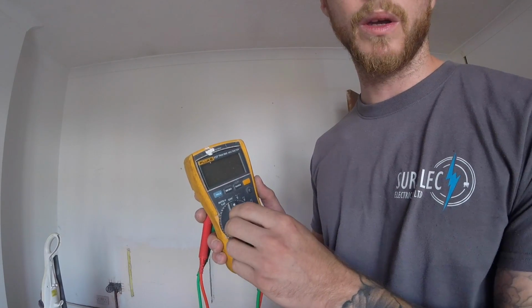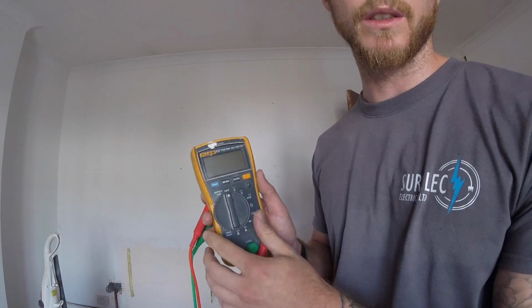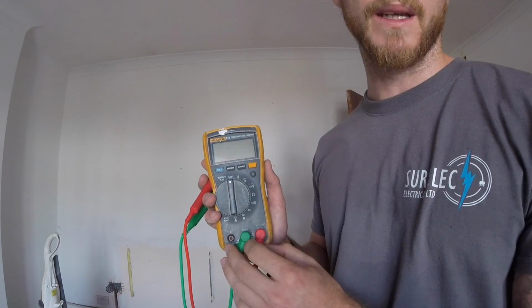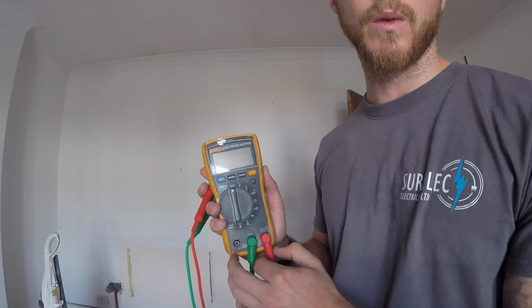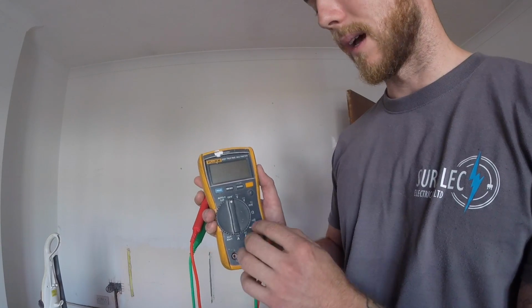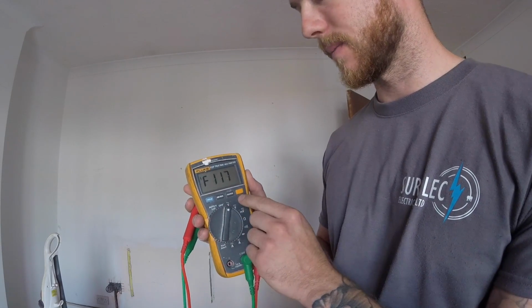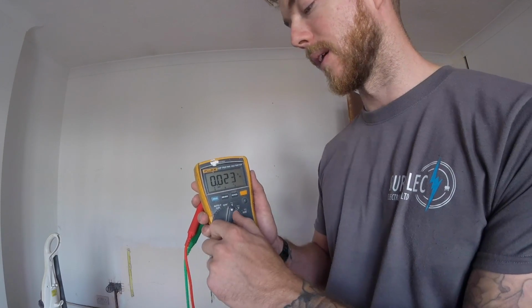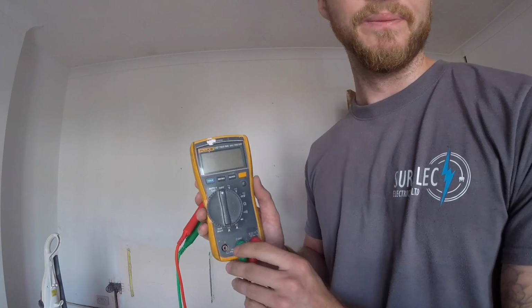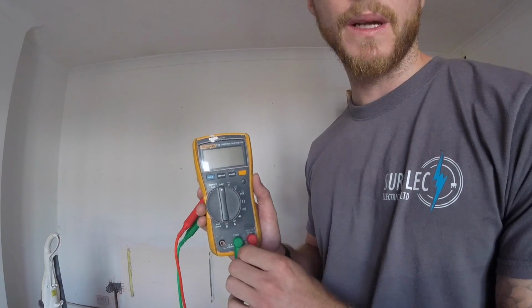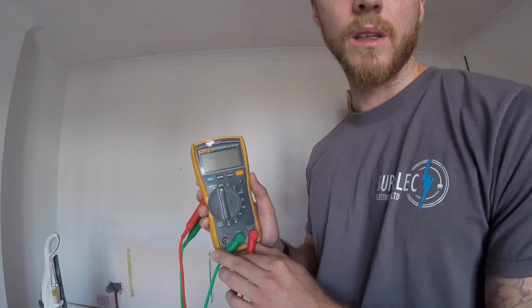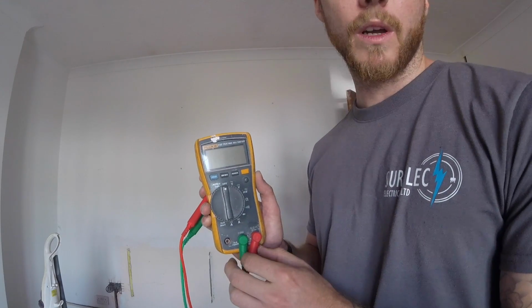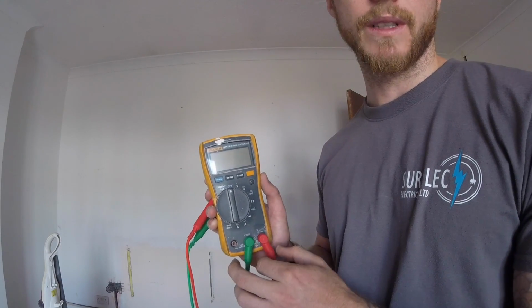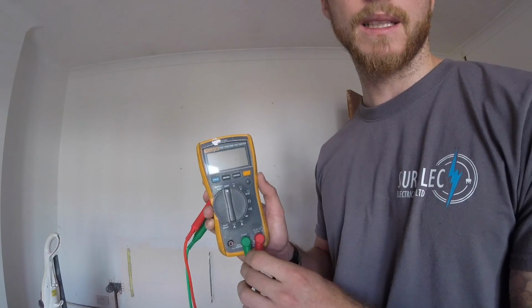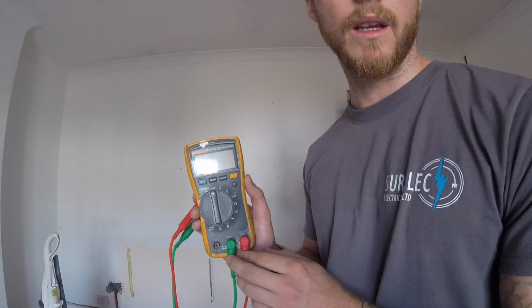So it's got low input impedance, which helps prevent false readings due to ghost voltage. It's got a large white LED backlight to work in poorly lit areas. I think the backlight on mine is nearly had it because it's not particularly bright now, but it is still there, so it does help, but not as good as it was when I first got it. It's got true RMS for accurate measurements on non-linear loads. Measures 10 amp, 20 amp overload for 30 seconds. It's got the option for resistance, continuity, frequency and capacitance. Obviously that's what the diode tester's for.